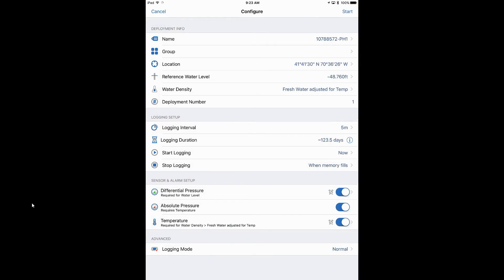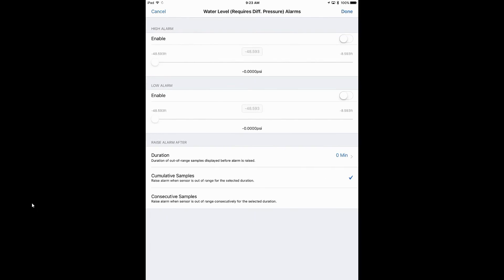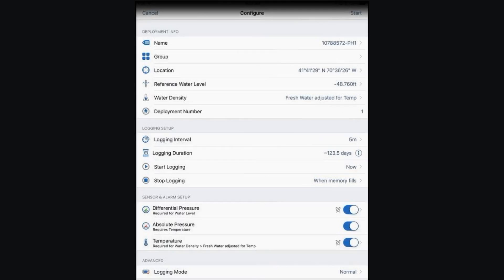We also give you the ability to set up alarms. These are just locally recorded — there's no external notification of alarm exceedance; it's strictly indicated in the data file when you read it out. Keep in mind that burst logging and alarms are mutually exclusive: you can either do alarms or burst, but not both at the same time. Now we're ready to put the logger in the water and press Start. We want to make sure it is in the water before we press Start because it uses that first reading as its calibration offset.